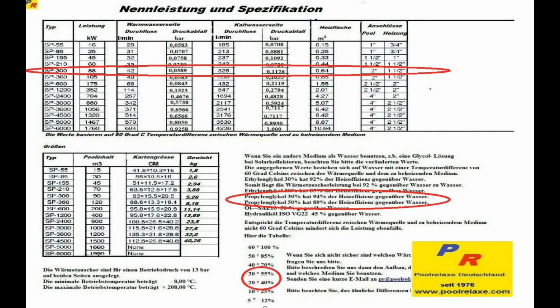A quick rundown on the math. The heat exchanger is rated at 88 kilowatts with about a 60 degrees Celsius temperature difference. Our expected temperature difference, however, is more between 20 and 30 degrees. At 20 degrees, we will have about 40% left. That rates our heat exchanger at about 35 kilowatts.